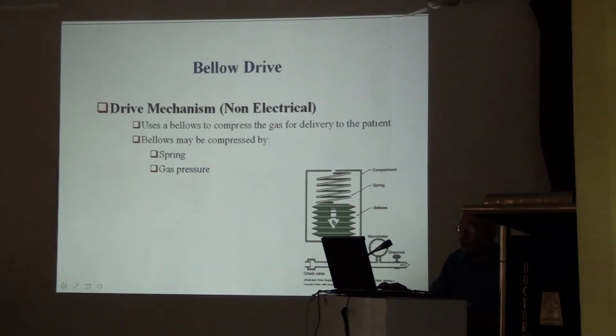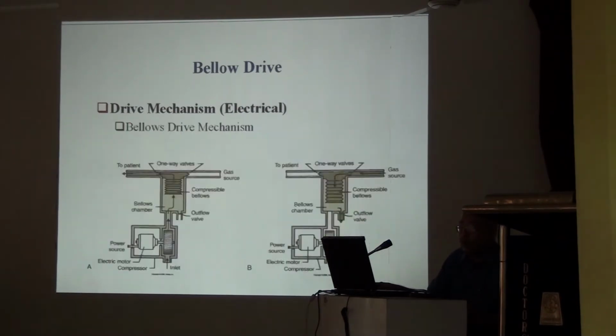Then the spring loading. There is a bellow concept in the back. Inside that there is a spring countered by the air force and the spring tension. The lung is inflated. I am not going into the details because I don't have time to go into the details of all these things. These are the motor driven ones. There is a motor. Here the blower pushes some air into the concertina in the back, so the air goes out through this valve to the patient. There is an inspiration and then an exhalation.